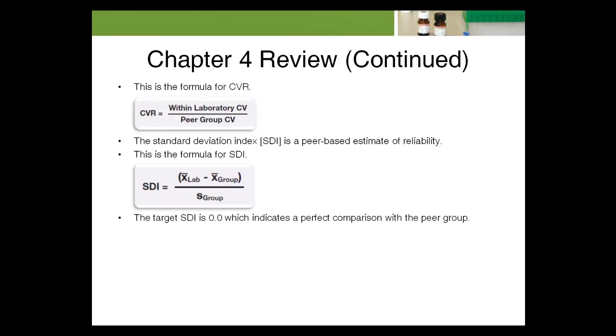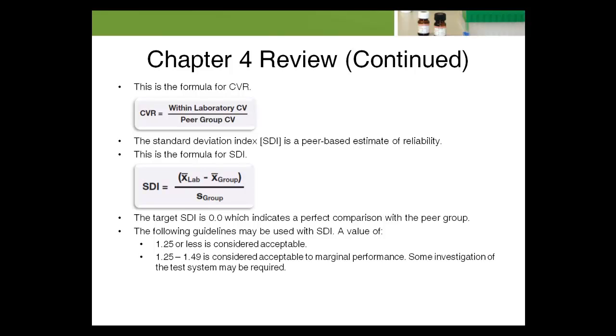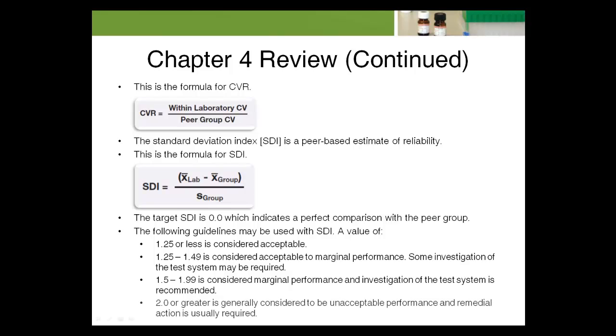The target SDI is zero, indicating a perfect comparison with the peer group. SDI guidelines: 1.25 or less is acceptable; 1.25 to 1.49 is acceptable to marginal; 1.5 to 1.99 is marginal and investigation is recommended; 2 or greater is generally unacceptable and remedial action is usually required.